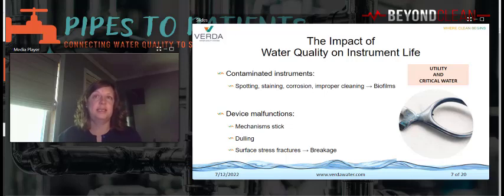Also, mineral deposits can act as seed points for corrosion to occur. The roughening of the instrument surface is where bacteria and biofilms can then take a foothold and be difficult to eradicate. It's more than having just good critical water for rinsing. Improper water quality for soaking and washing can also result in inactivation of the detergents or cleaning enzymes. This results in inadequate cleaning, which can provide surfaces on the medical device for microorganism growth.